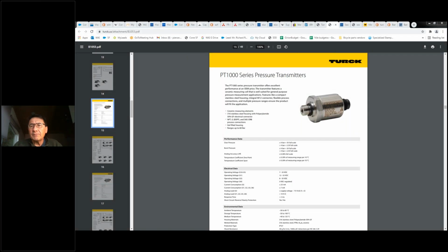And they all pretty much come out in this form factor. It's basically a stainless steel barrel. Make sure you get a type 316. There are some less expensive sensors out there in type 304. Not as good a grade of stainless steel, tend to corrode after a while. Type 316 is a very robust anti-corrosion steel. These sensors are field installable outdoors, no issues.